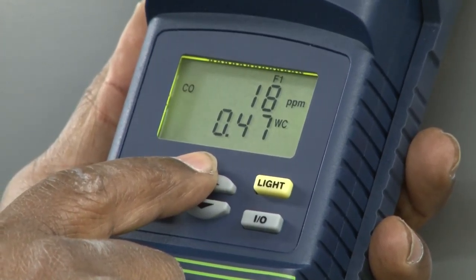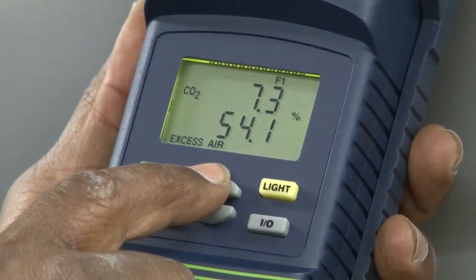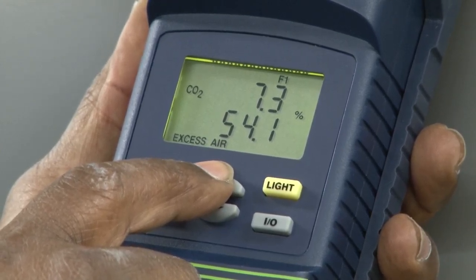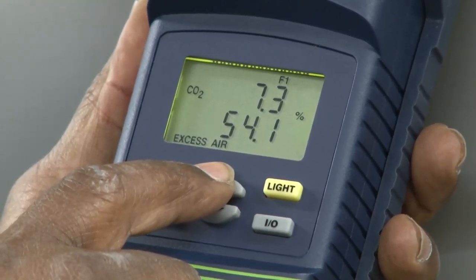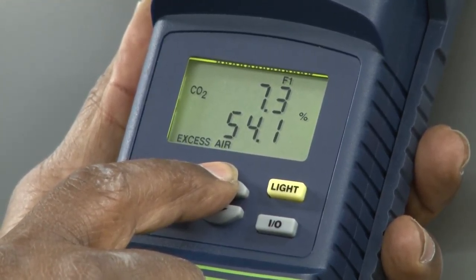Our static pressure, in inches of water column, is 0.47. Our carbon dioxide is 7.3, which can be a little bit higher than that, which will probably reduce our carbon monoxide.